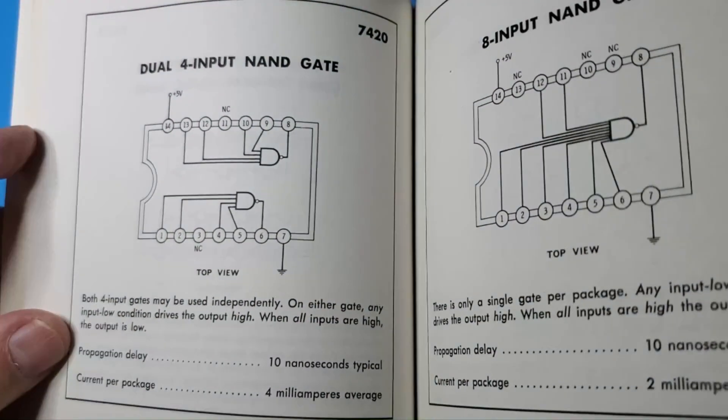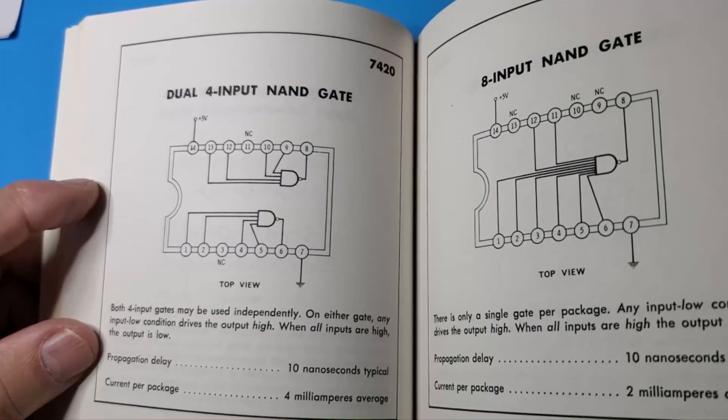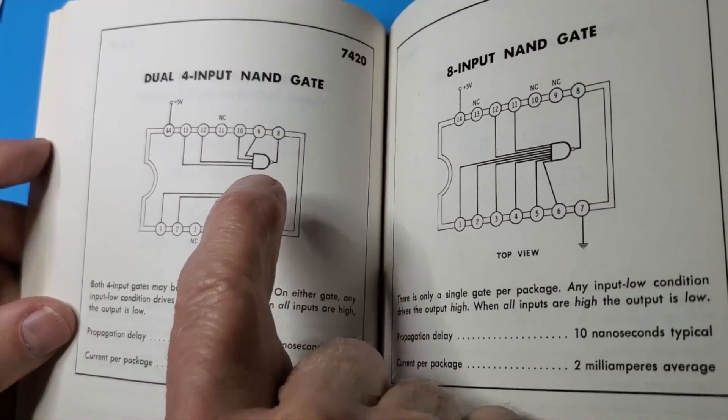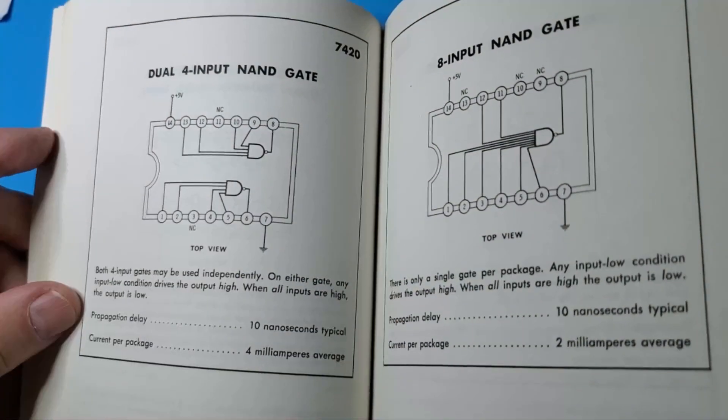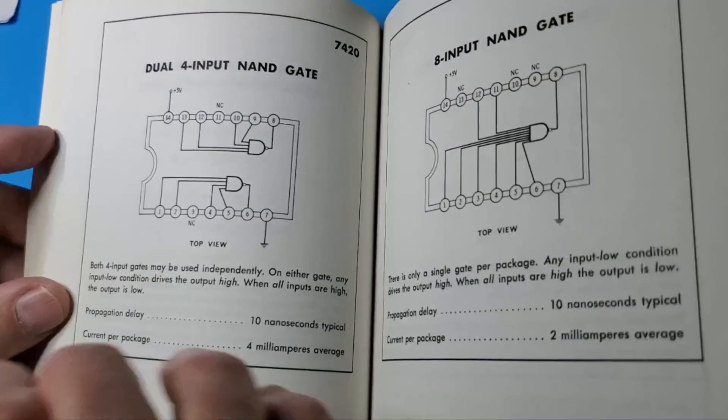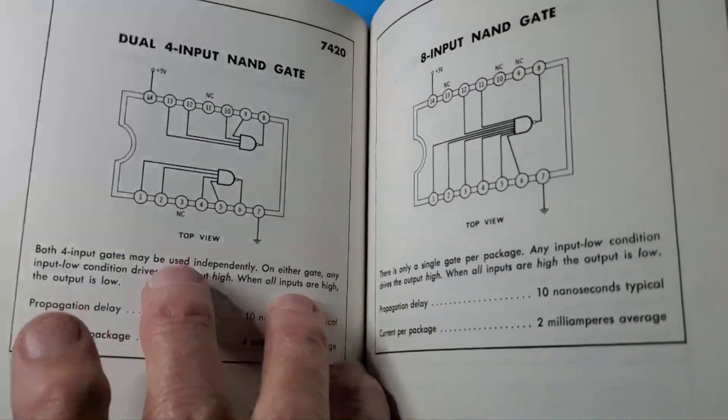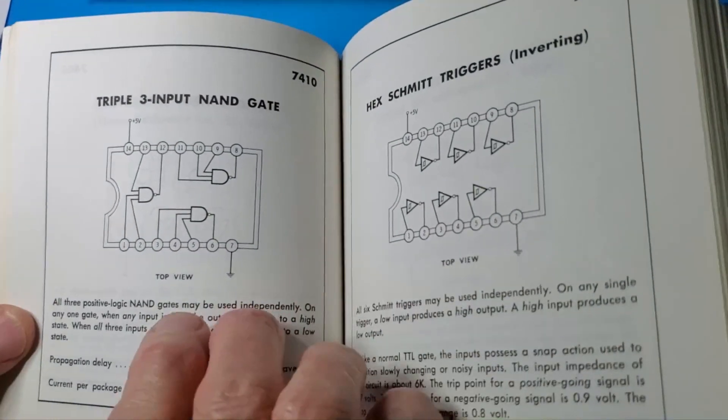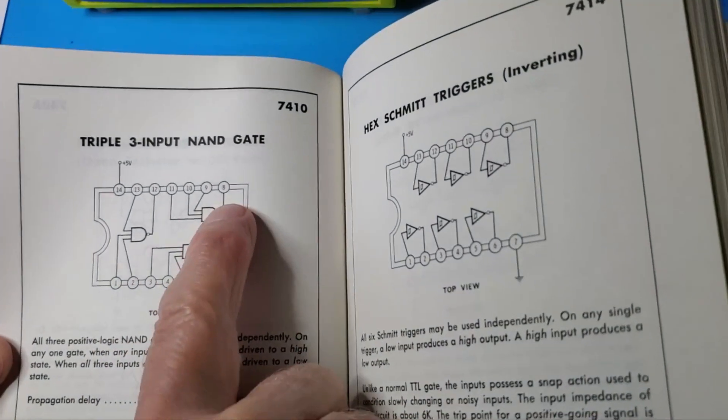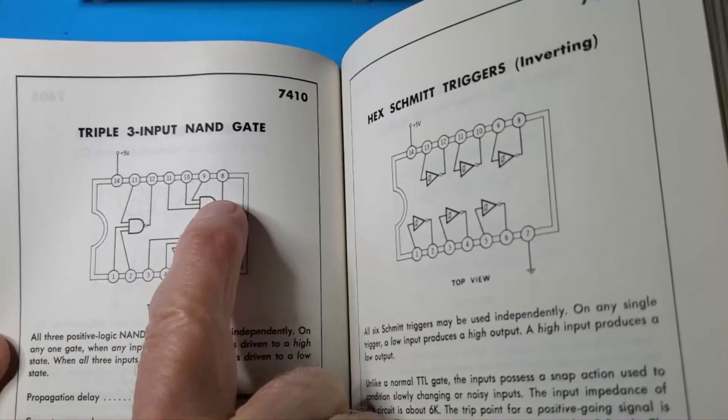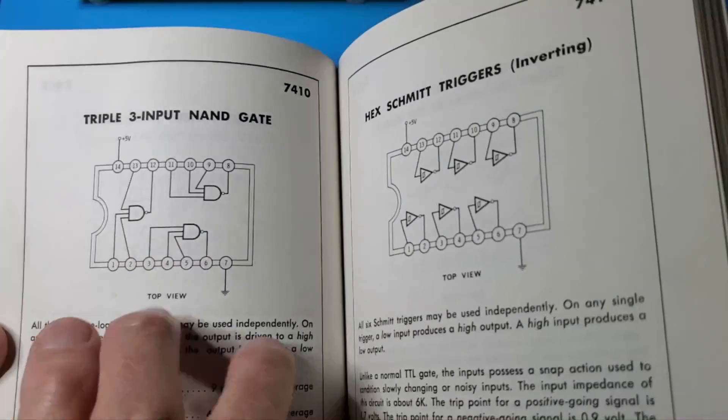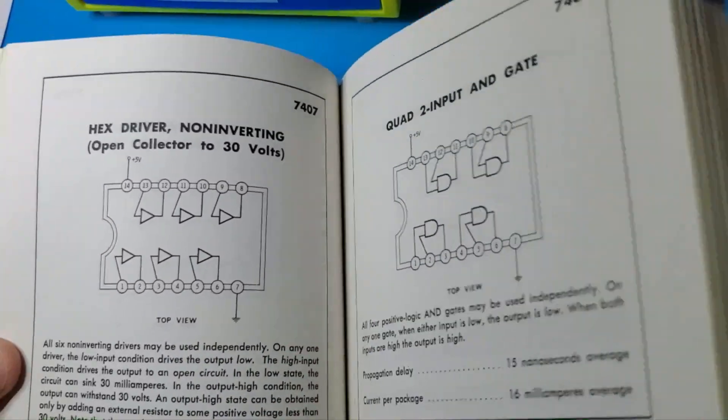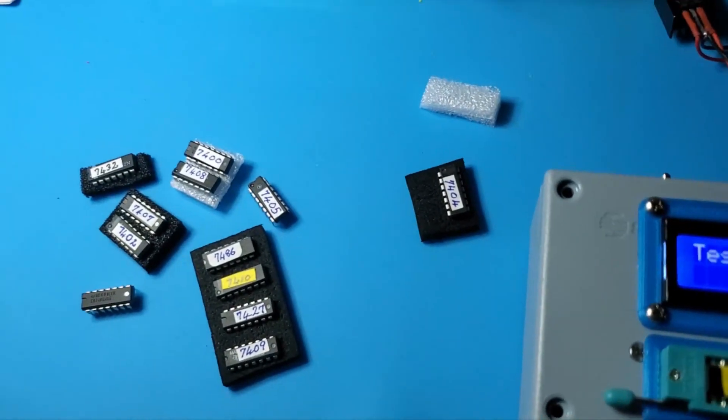It doesn't do like nine and ten true and twelve and thirteen false. It just tests them one at a time when it's more than two inputs. If it's two inputs, it tests all combinations. But it's likely they're all working if individual inputs pass. That's pretty much a good test.